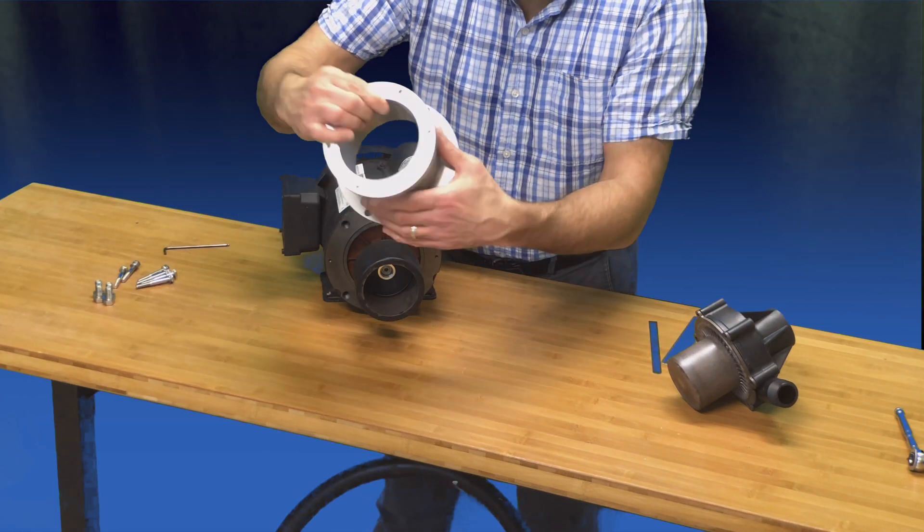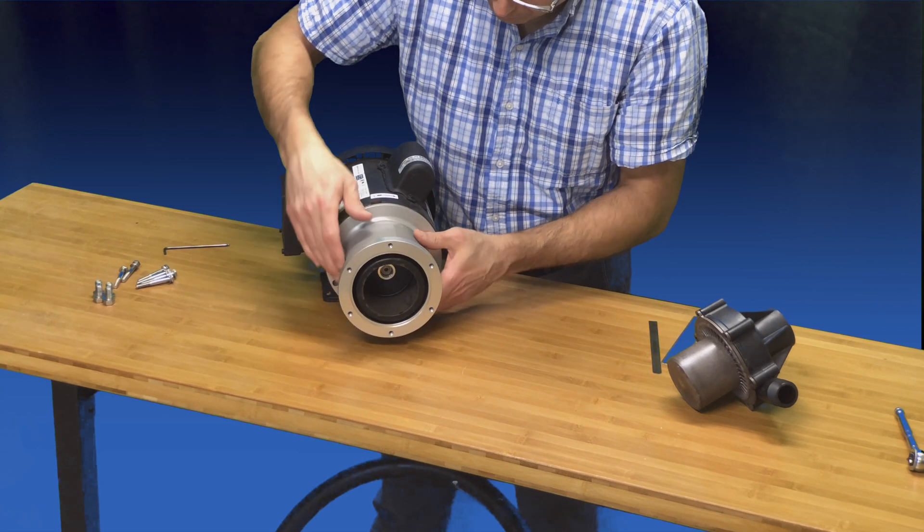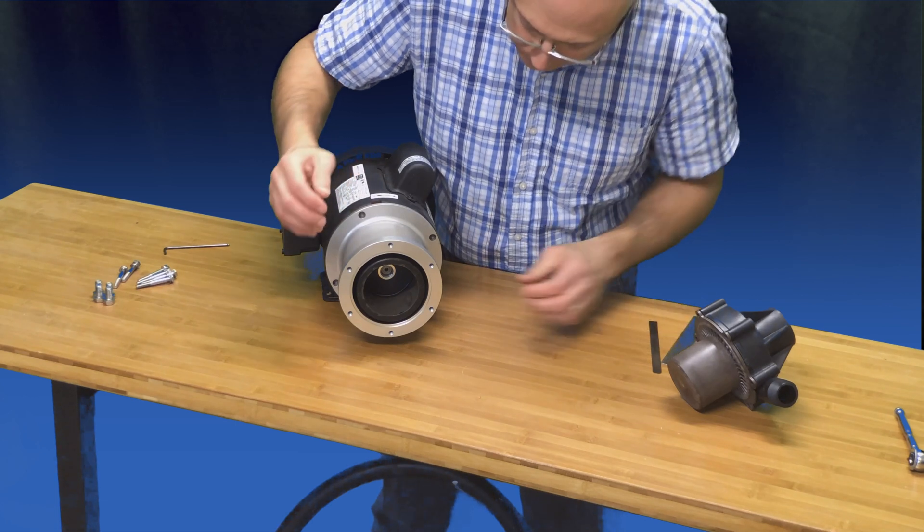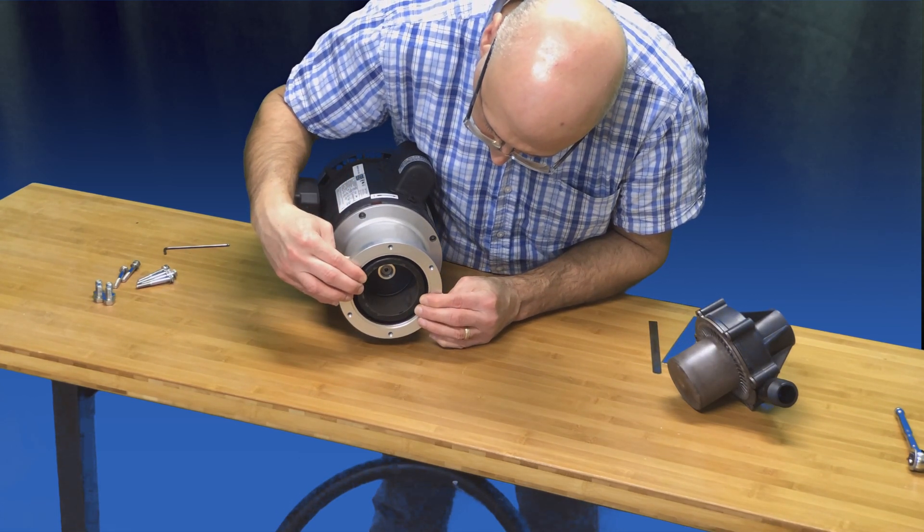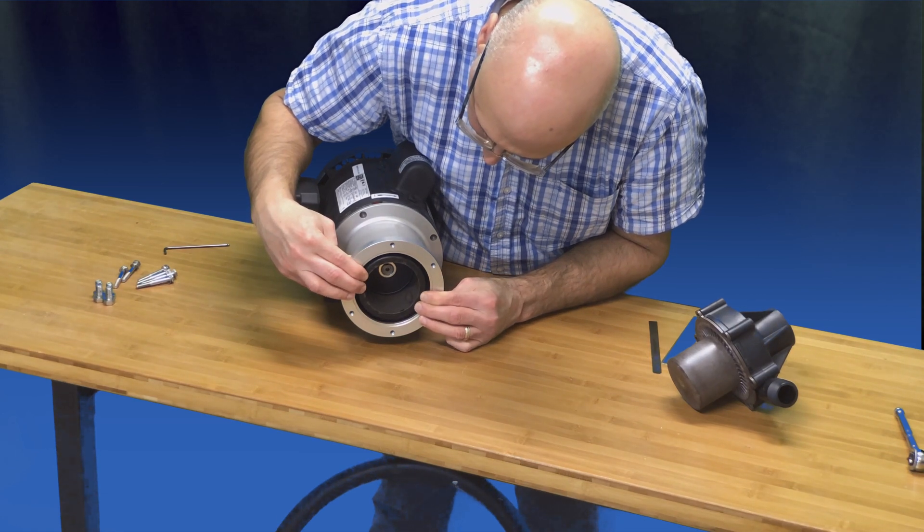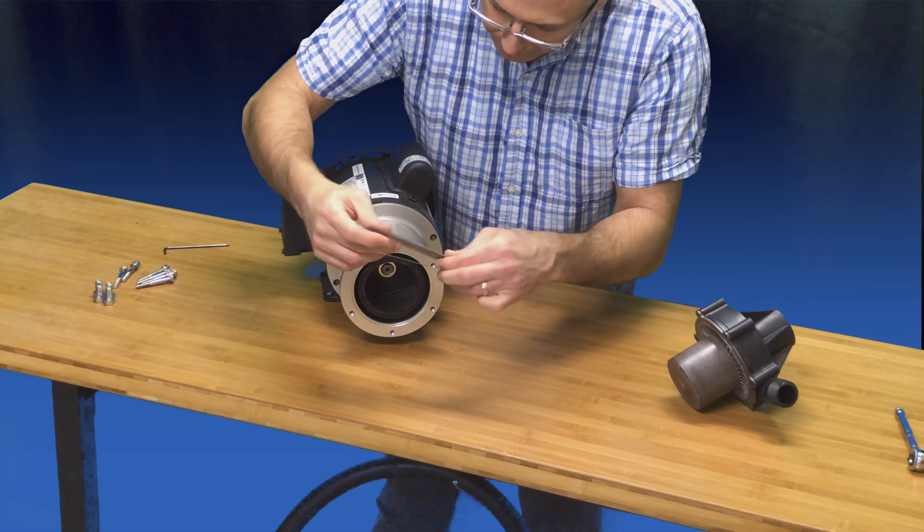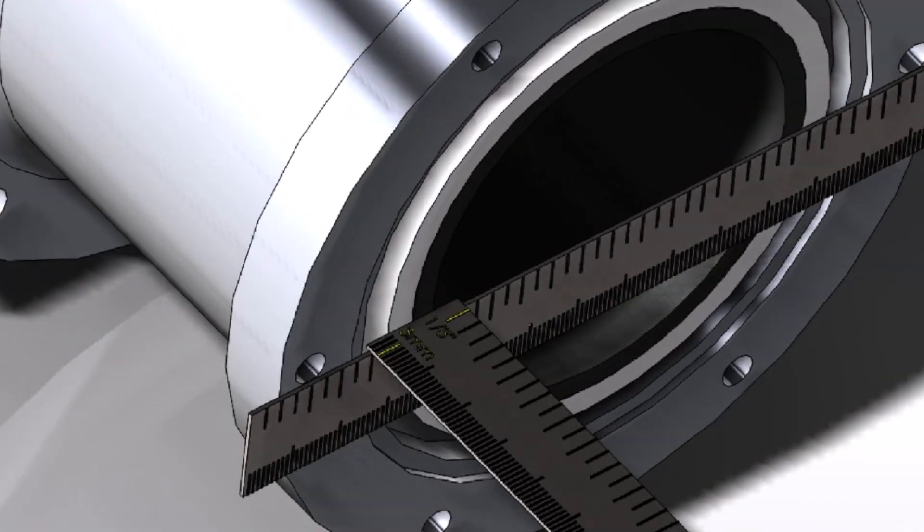Next, seat the motor bracket against the face of the motor. Then push the drive magnet assembly in so that its face is slightly below the front face of the motor bracket. Now take the two straight edges and use them to help position the drive magnet assembly one-eighth inch below the front face of the motor bracket.